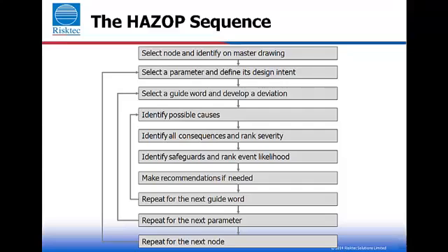What safeguards exist to prevent the hazard occurring in the first place? Do we have control systems? Do we have valve position indicators? And then what corrective actions can be applied to prevent or mitigate against the hazard progressing towards its consequence? What shutdown systems are there? Are there pressure relief valves in the system? The process is then repeated for each guide word, and for each parameter, and for each node.